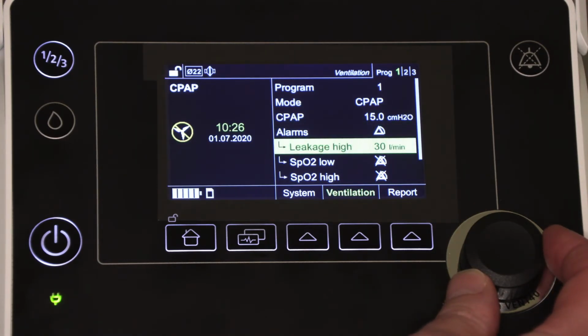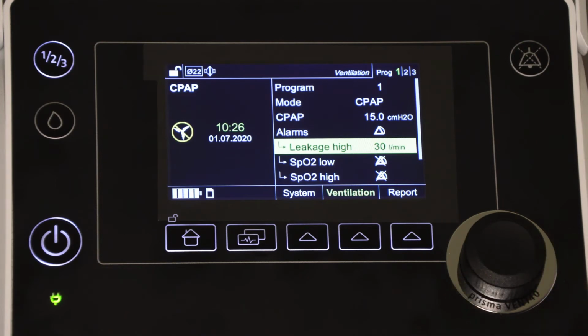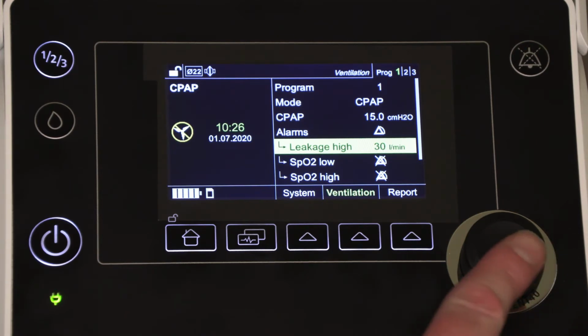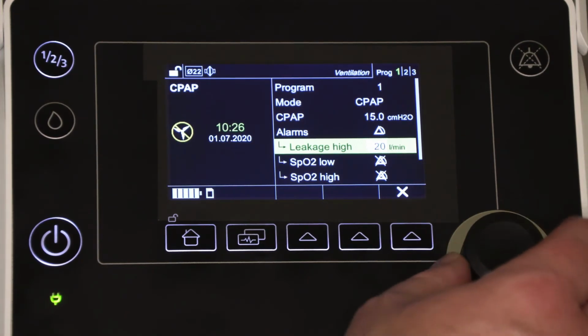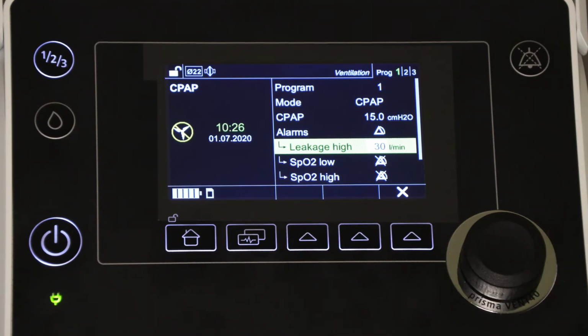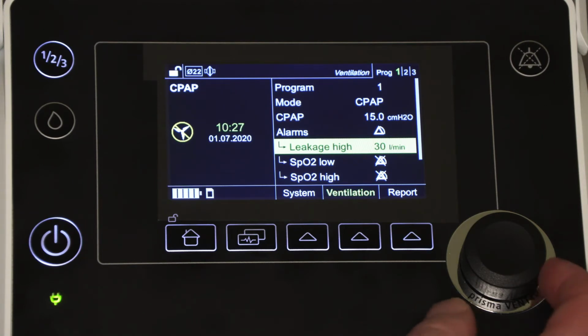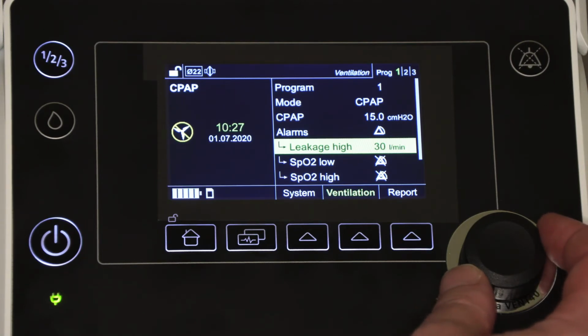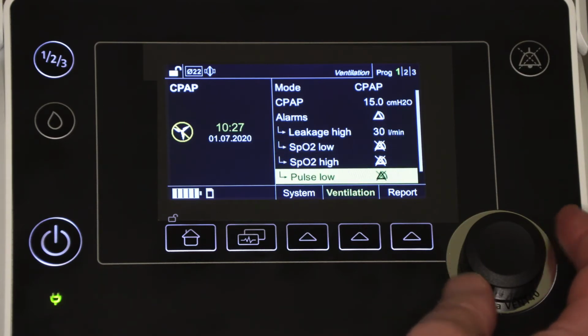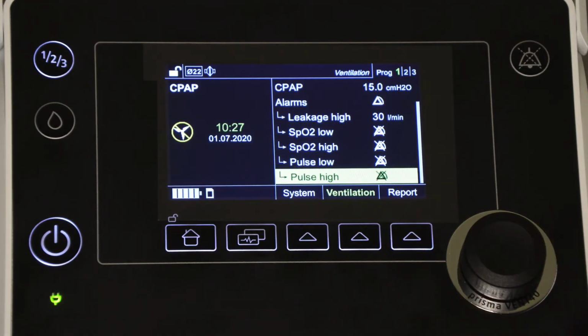The high leakage alarm warns of excessive leak around the mask or in the breathing circuit. So if you want to be alerted if the leakage around the mask exceeds, for example, 30 litres per minute, then set the alarm to this value. This value can be adjusted if you want the device to allow for more or less leak before being alerted by an alarm.